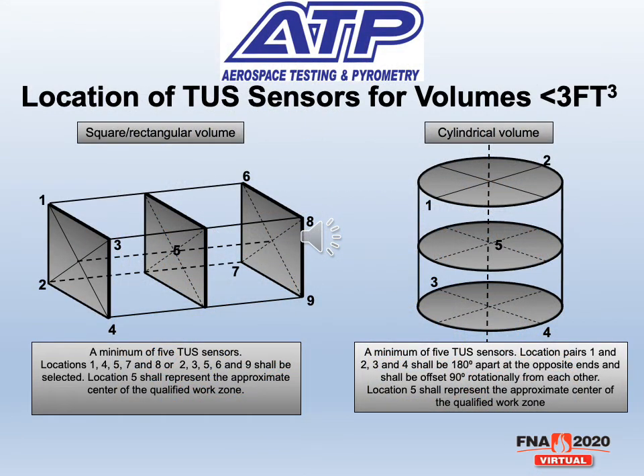We address the location of TUS sensors for volumes that are less than 3 cubic feet. In AMS 2750E, it was ambiguous where those thermocouples needed to be located. For instance, in a square or rectangular furnace in Rev E, we just said 4 thermocouples needed to be in the corners and 1 in the center. So we've updated what the expectations are for work zone volumes that are less than 3 cubic feet. In this instance, if you're choosing your 4 corners here and you want to choose locations 1 and 4, that's acceptable. Then you would have to use locations 7 and 8 in the back of the furnace, which is opposite corners from the front zone, and then again 1 in the center. For a cylindrical furnace that is less than 3 cubic feet, you'd have your top thermocouples 180 degrees apart from each other, and the bottom thermocouples 180 degrees apart from each other, but those would be 90 degrees perpendicular to the top of the furnace, again 1 in the center. This gives us a better look at what the furnace is doing from front to back and top to bottom in these locations.